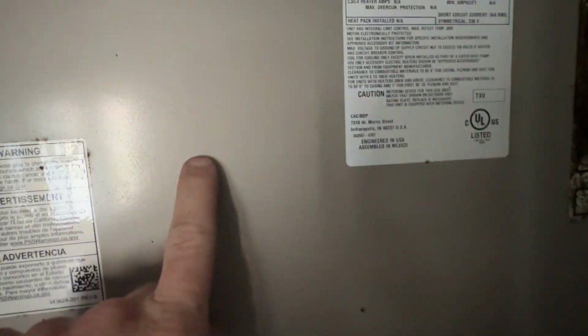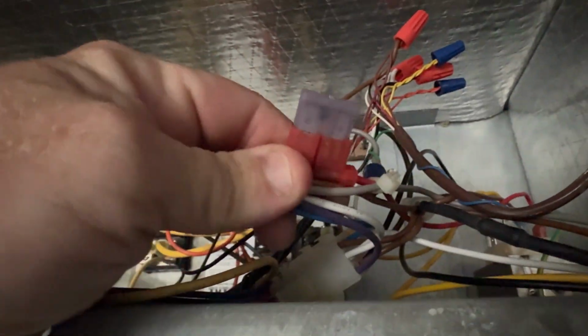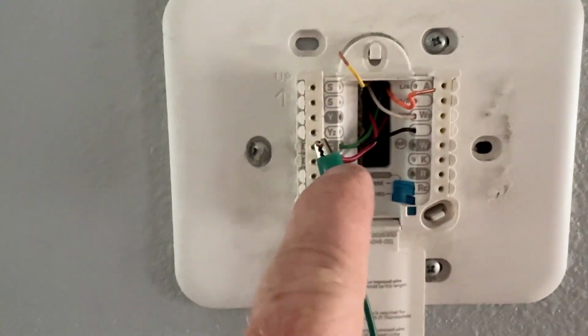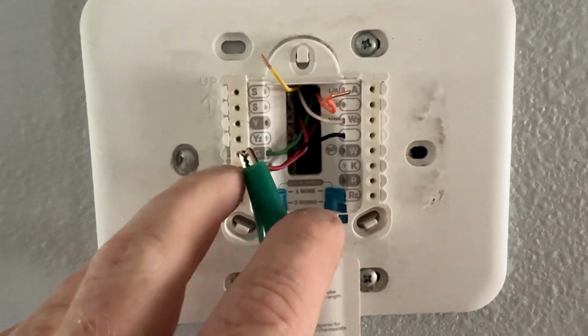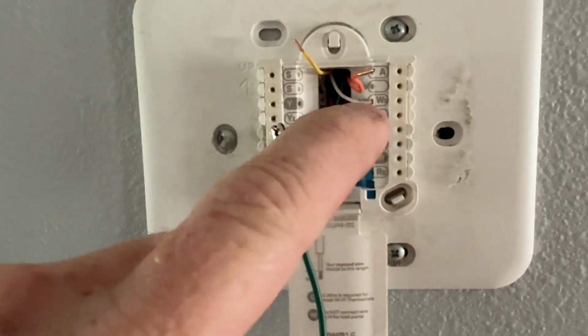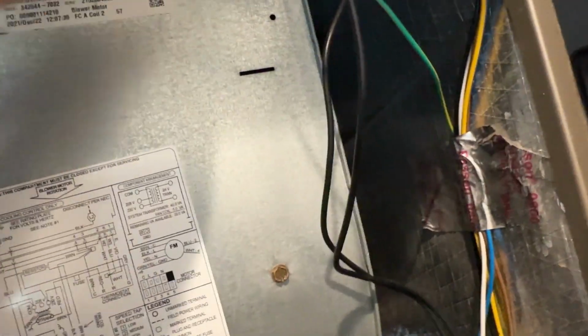Power disconnects on. Float switch is clear. We're gonna pull this off and check the fuse. We have a pop fuse, so we'll look for a short. But in the meantime, actually it looks pretty good. Just a little bit of normal mildew. Looks good though. So I pulled the thermostat because we're getting this fuse tripping instantly. So I put this on here and it trips the fuse without the thermostat. So we have something else going on, a short. It's probably direct to ground somewhere, so we'll find it.